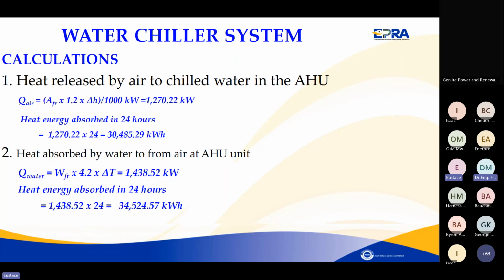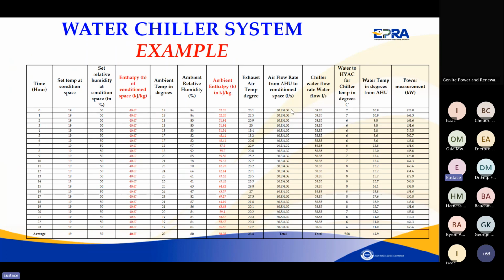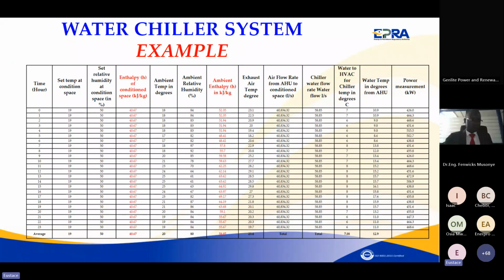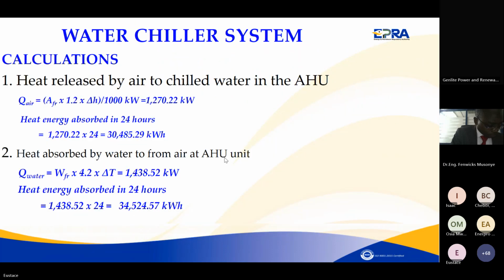So after you have measured and recorded that data, and when you have done an energy audit, this is the first data we would like to see. When you do your calculations, we want to see the source of this data, even your client and everybody, because we need some form of traceability. So in that case, you can calculate the heat released by air to the chilled water using that formula. Everybody can see that.